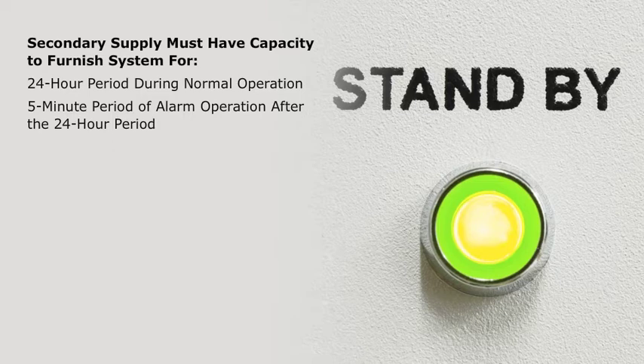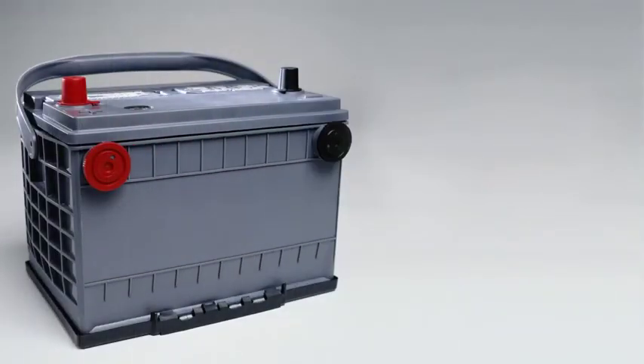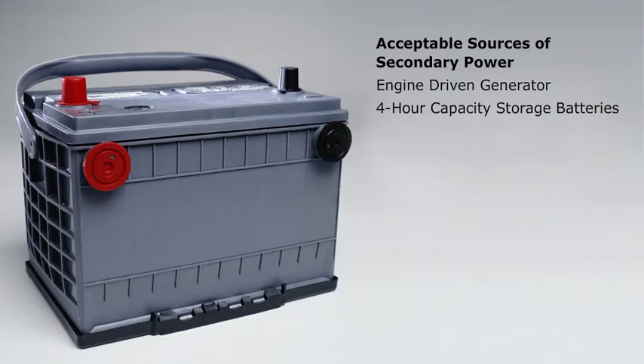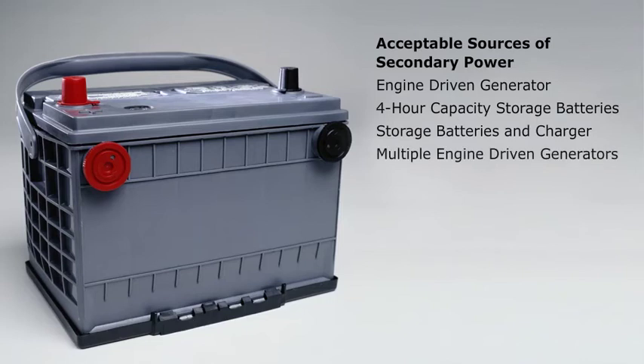This is also known as 24-5 capacity. Some acceptable sources of secondary power would include engine-driven generator and 4-hour capacity storage batteries, storage batteries and charger, and multiple engine-driven generators, one of which can be equipped with automatic start.